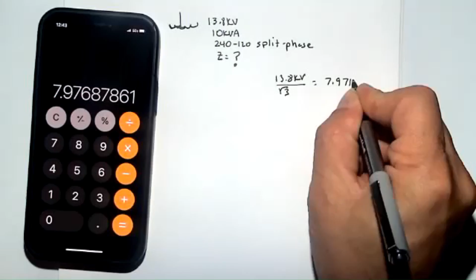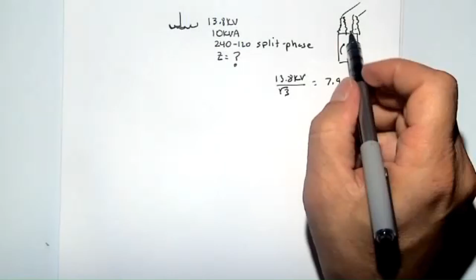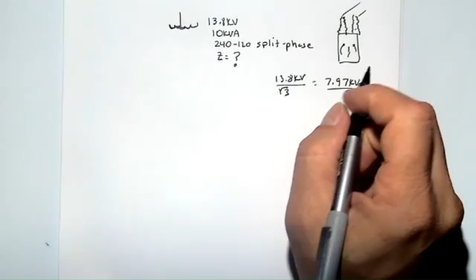You'll see your secondary bushings coming out of the secondary here, the 240 volt and the center tap grounded neutral coming off there. If there's only one tall bushing and one short bushing, then a lot of times it's rated line to neutral. They do that because the cost of the bushing adds up across the many, many transformers that are out there. So sometimes they apply them at a line to neutral rating, or in this case, line to ground, and sometimes at line to line. But we're going to just say it's line to line for this one.